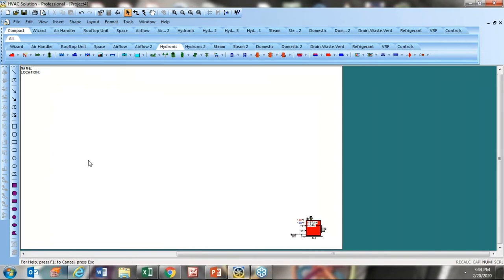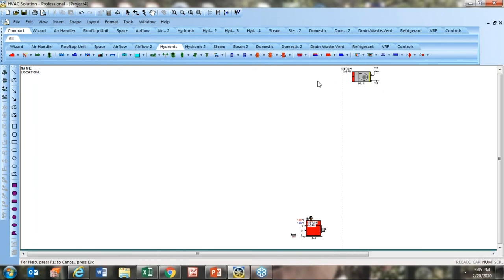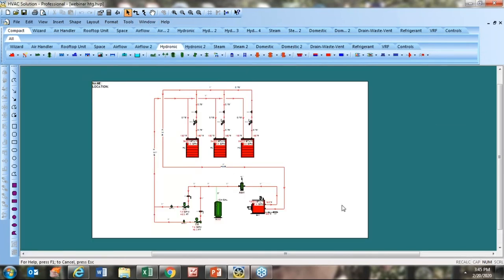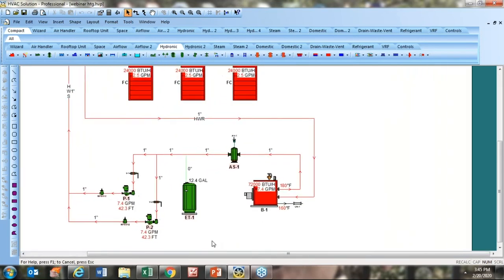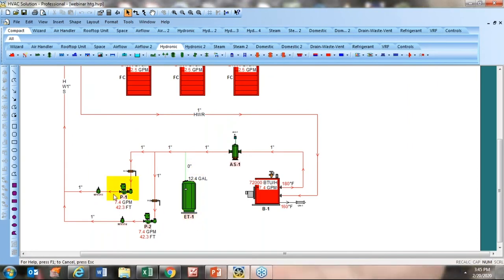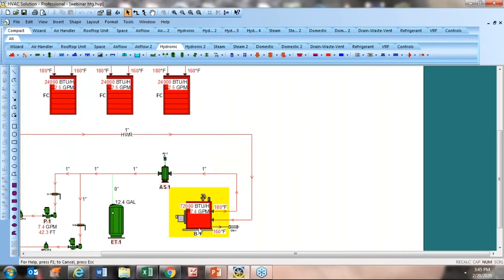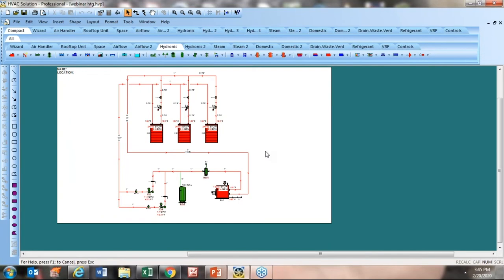I'm going to represent some loads here and draw a very simple diagram. I go way down to the Hydronic Heating Imposed Load, click the down arrow, go to Terminal, get a fan coil, and drag and drop it. Here's a simple design I put together just before the webinar — you can see some of the information the software will produce: sizing expansion tanks, sizing the pump for flow and head, keeping track of that information for schedules, pipe diameters, and boiler sizing.